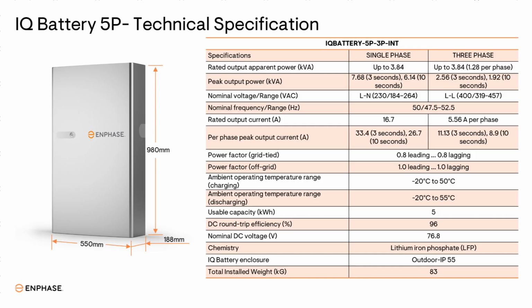Nominal voltage range is line to neutral 230 volt, with a 184 to 264 volt range. Line to line is 400 volt, with a 319 to 457 volt range. The frequency range is 47.5 to 52.5, and the rated output current is 16.7 to 5.56 ampere per phase. Power factor is 0.8 leading to 0.8 lagging. Power factor off grid is unity in off grid scenarios. The ambient operating temperature range is -20 degree to 50 degree centigrade during charging, and during discharging -20 degree to 55 degree centigrade. Usable capacity is 5 units stored inside this battery.